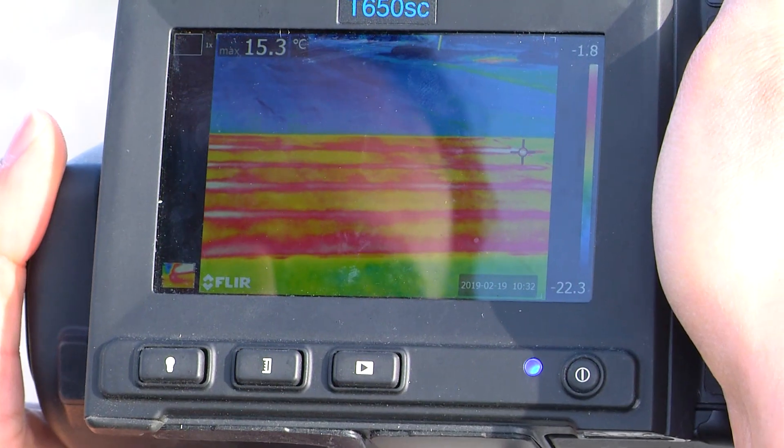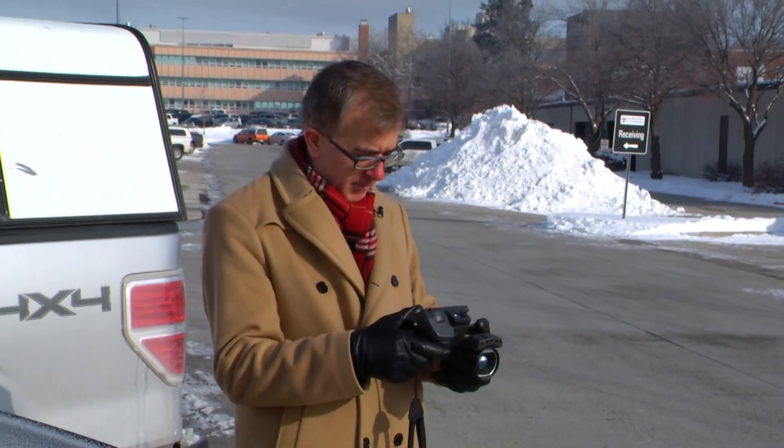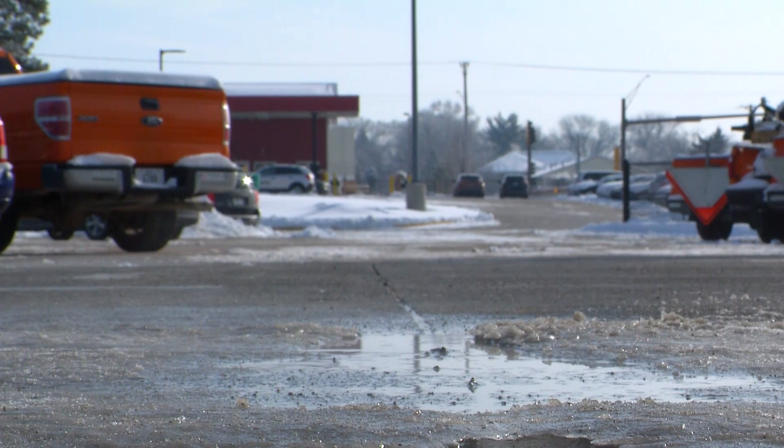The system is working really well, and when we turn all the slabs on, we can actually see the heating taking place right away. When we look at the thermal imaging system, you can see the red areas — the heated concrete — versus the blue areas, the cold control slabs. We are successfully able to melt it away, and you can see steam coming out on the other slabs.